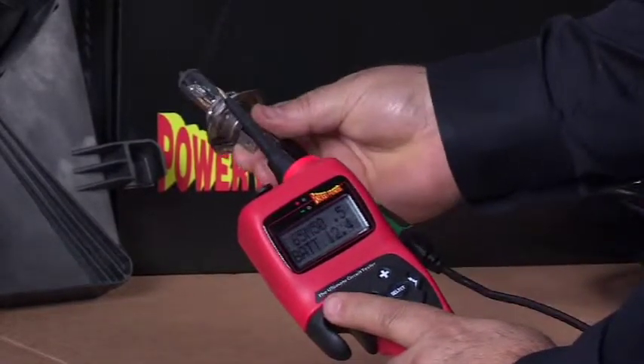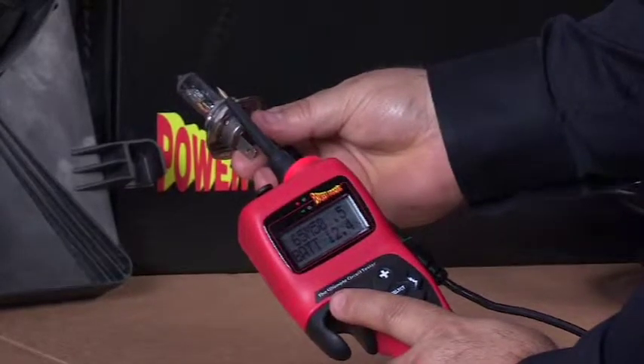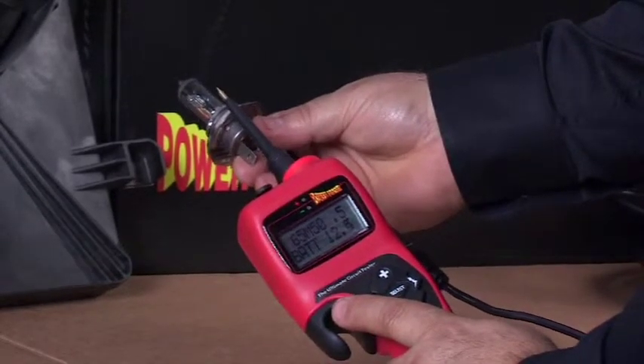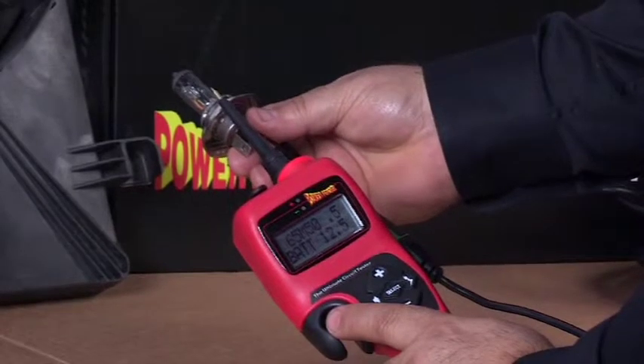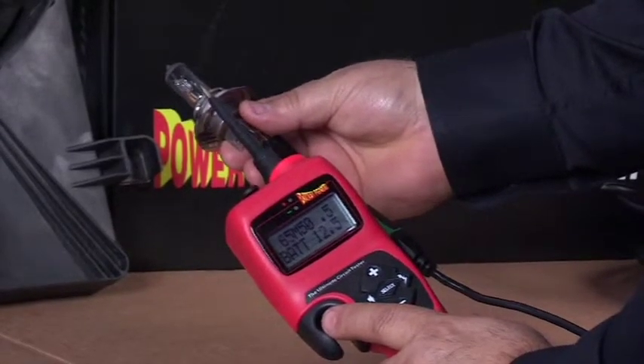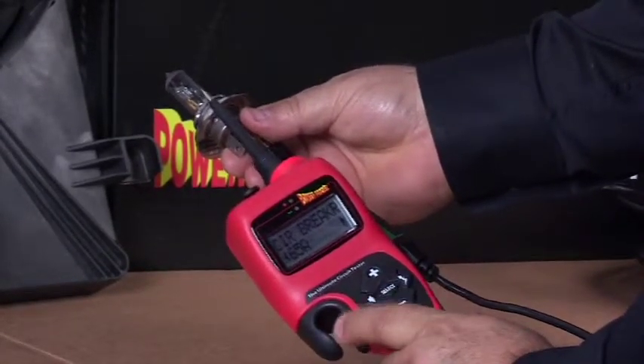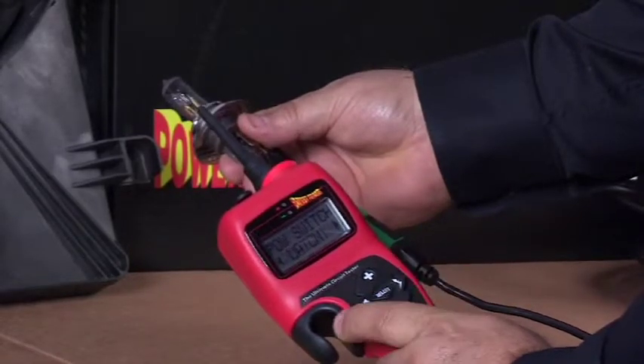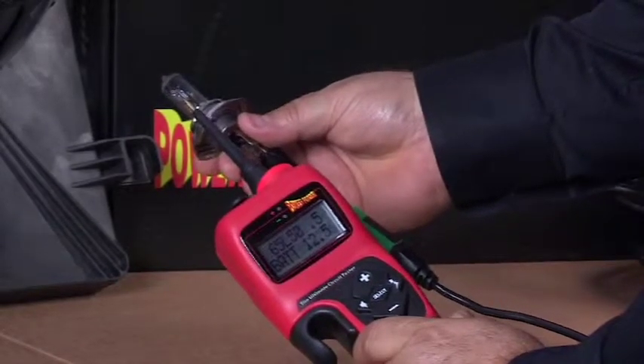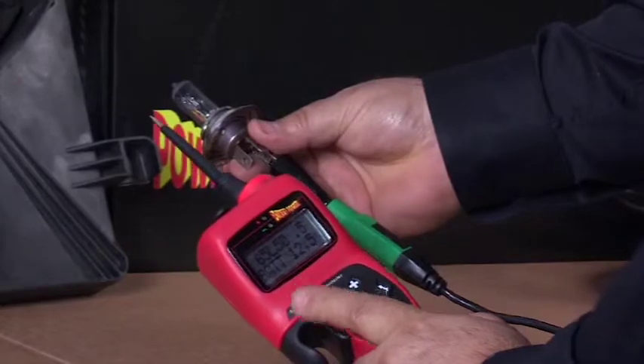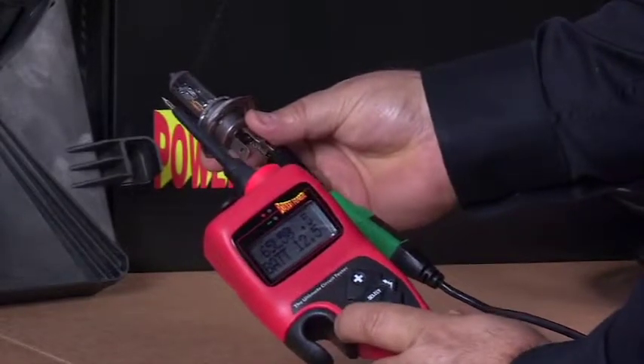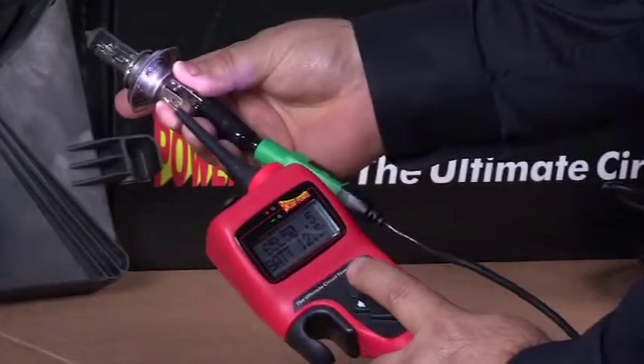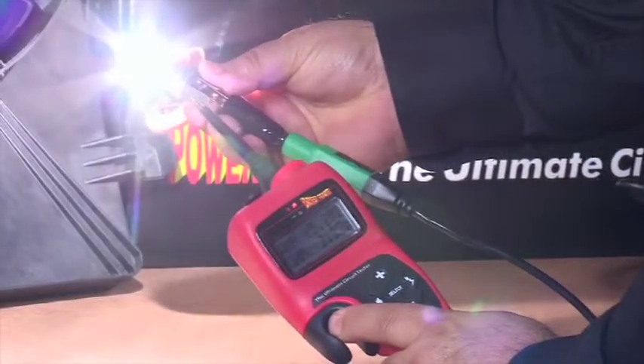To hold power on the probe tip so you don't have to continuously hold the power switch, set the power switch preference to latch like this. Press select, down, right, select. Notice the L in the preference line right after the circuit breaker trip point. Now press the power switch. To cease power, press the power switch again.